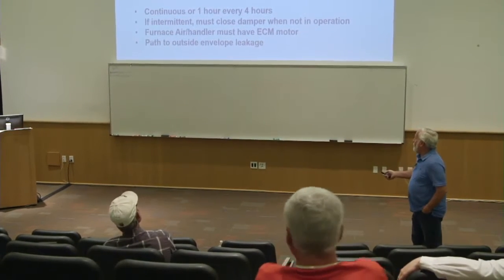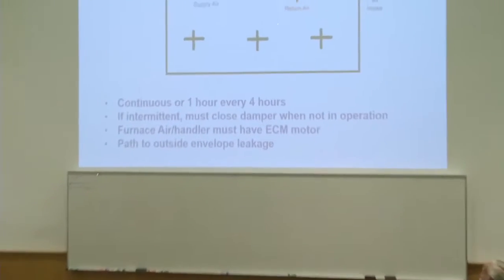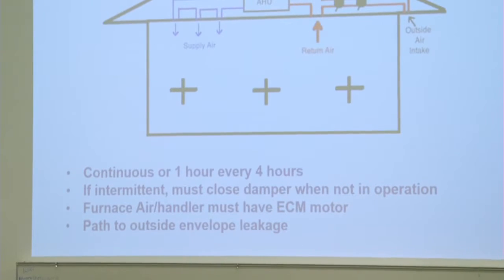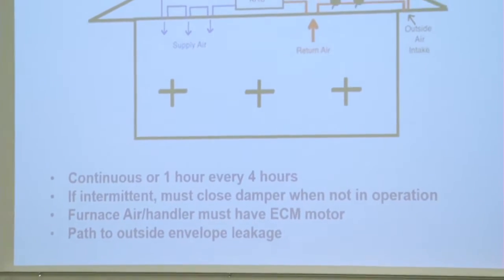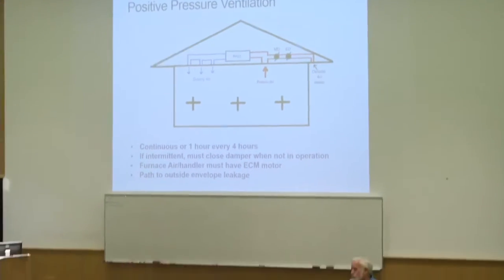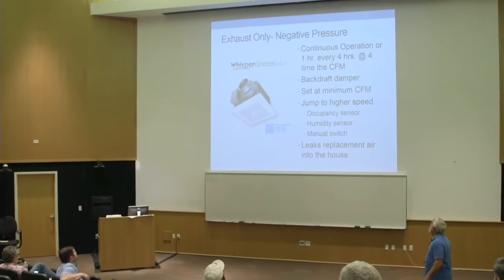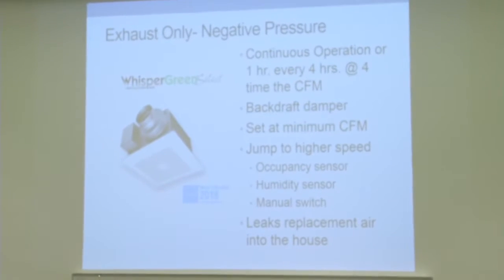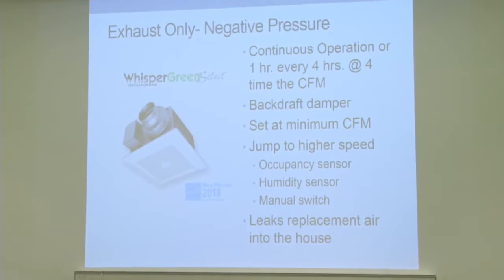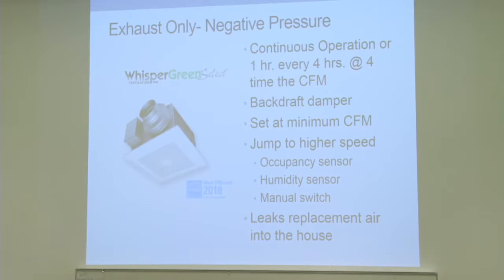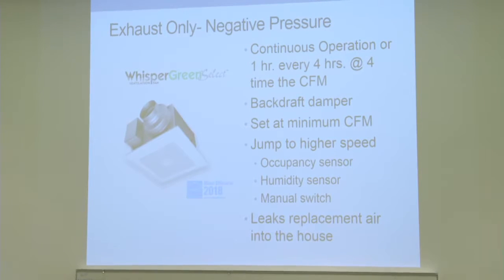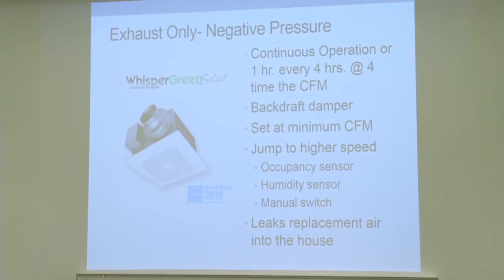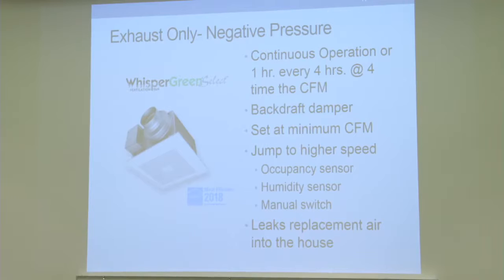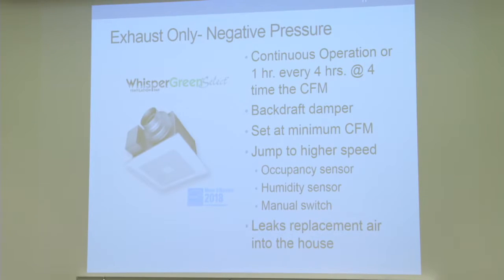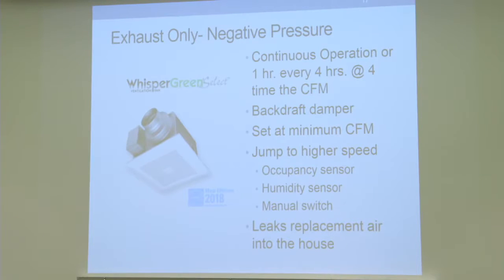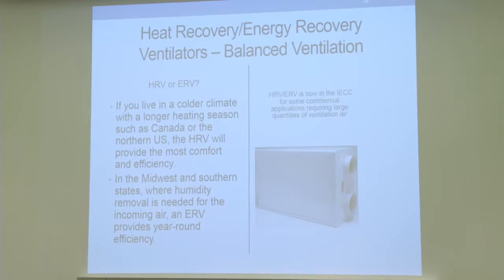When we're doing this, the path to outside, so we're positive pressuring, the path to outside is what? Leakage. We leak air out of the house. That's our, quote, exhaust air, what we push out by positive pressure in the house. Here's our fan. Continuous operation, or 1 hour every 4 hours, backdraft dampers, same requirement, set at a minimum CFM, jump to a higher speed by one of those three, and maybe they have something else you can do to bump it up. And leaks into the house replace the air that you exhaust. So you get your fresh air in by leakage, where with positive pressure, you bring in your fresh air and exhaust by leakage. Then HRV, and we'll wrap up on this real quick.